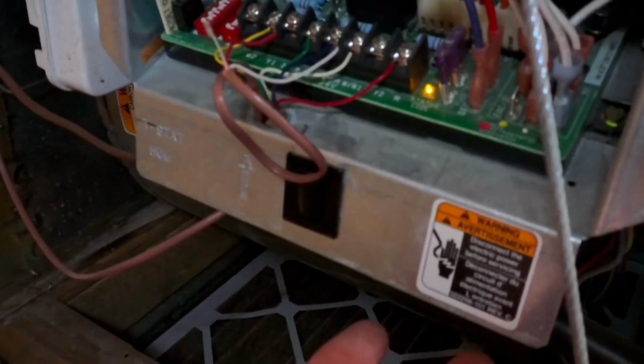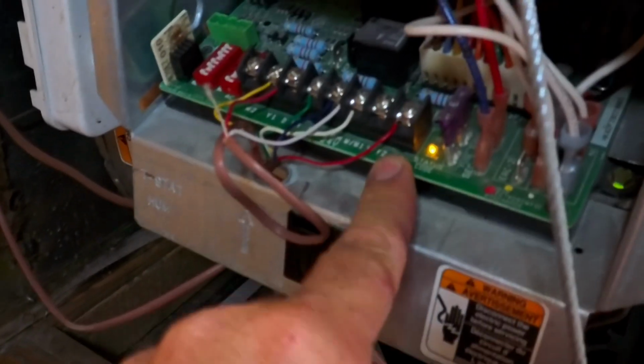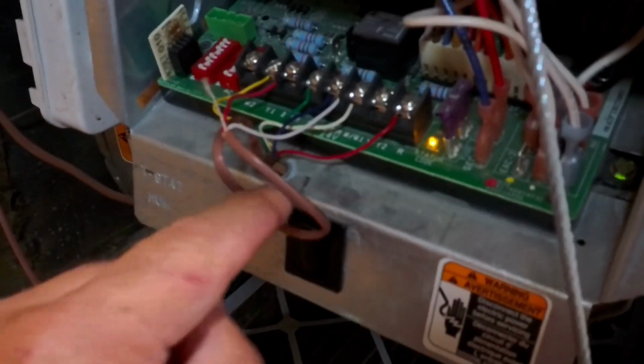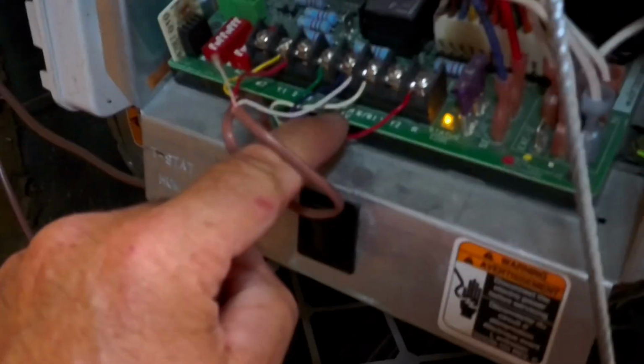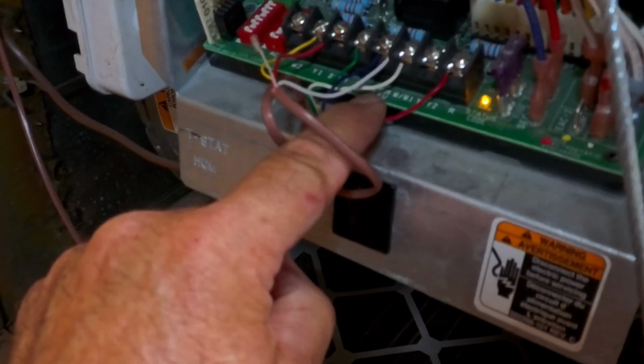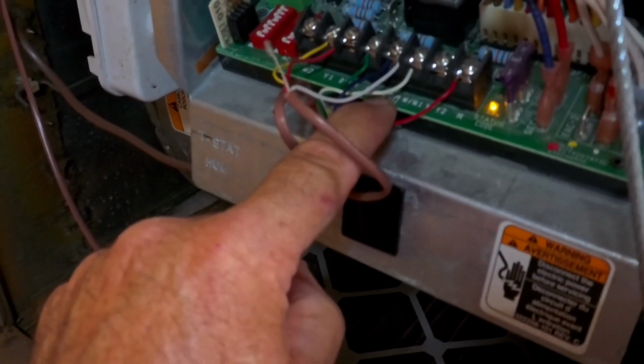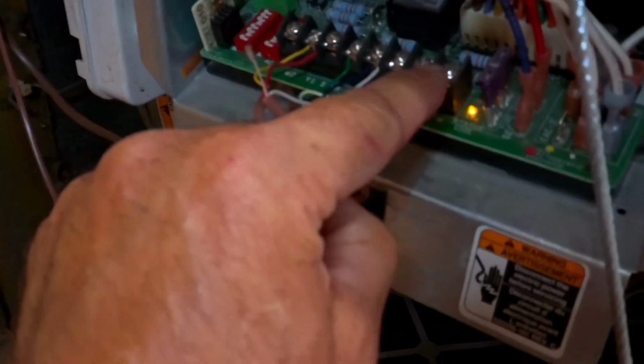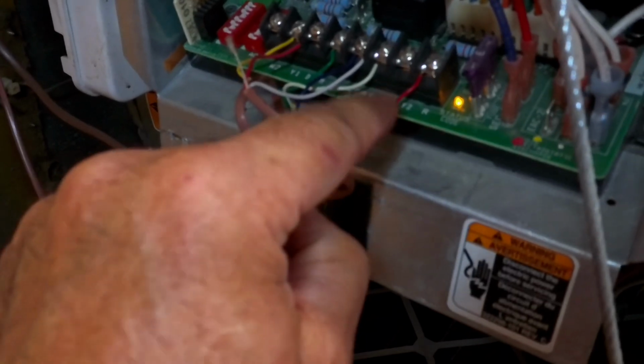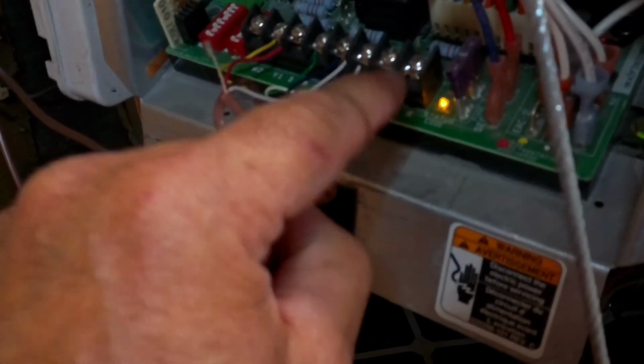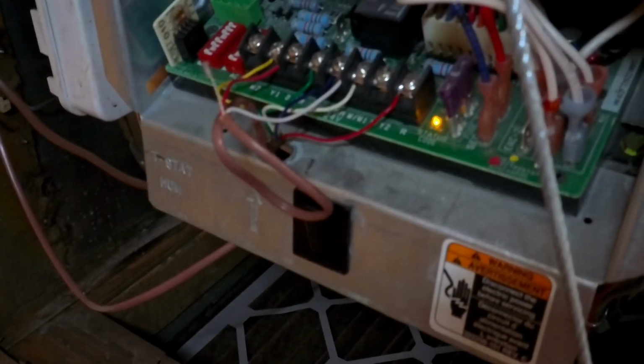So the transformer sends 24 volts to the R terminal, and then either the C for common, or on my setup here it says common 24 volts. So basically if I measure voltage from the common to the R terminal, not the red wire, the R terminal, I should have 24 volts. So let's check that first.